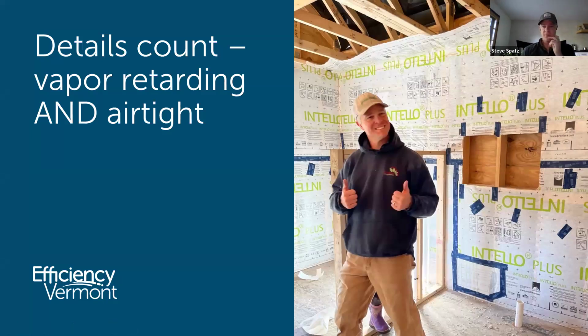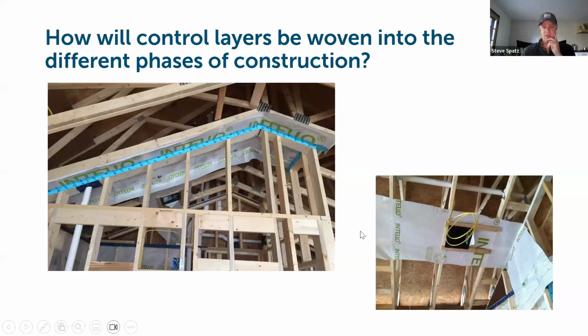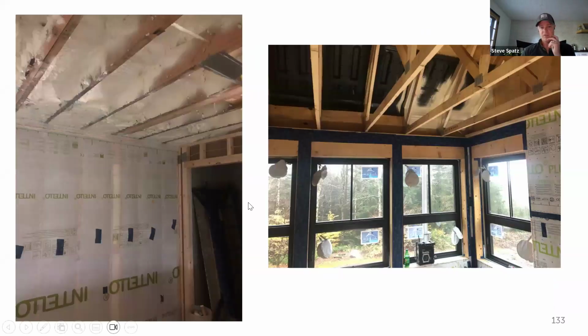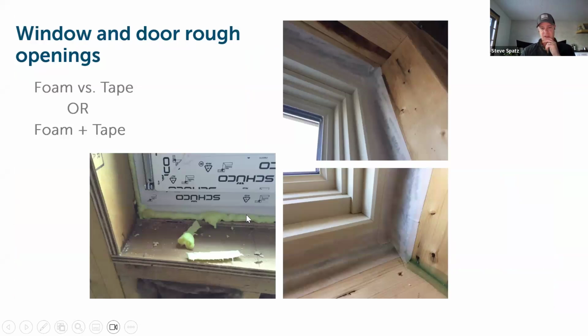The details are really what matter here, making sure that materials are installed consistently and made airtight, because you are stitching together multiple pieces of material to create an assembly and a whole. So really looking at the perimeter of the space that you're detailing, making sure that the vapor control layer is glued at your top stud, your corner stud, your bottom plate, and any window and door rough opening is also sealed up as well. So these are, again, just some of the details that need to be accounted for on the passive side of things before we get into the mechanical side of things for ventilation.